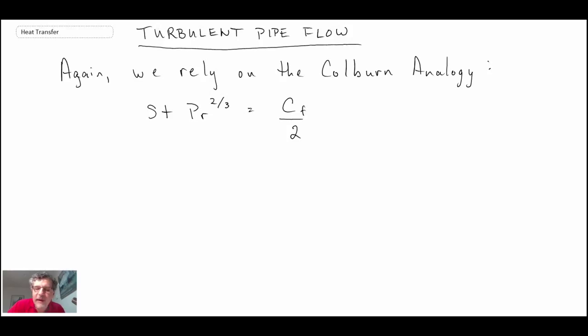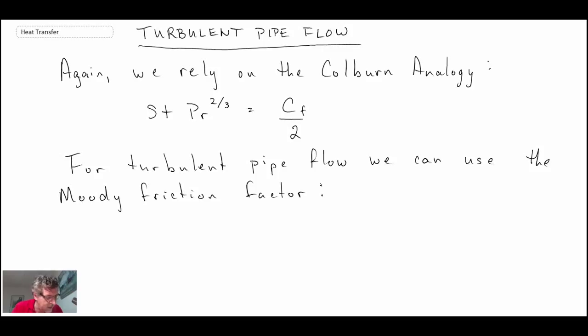So what we're going to do, we're going to come up with the skin friction equivalent for pipe flow. We'll be using the Moody friction factor and this friction factor can either be obtained from the Moody diagram or it could be obtained from something like a Colebrook-White equation. From the friction factor we can relate it to pressure drop and in this expression L is the length of the pipe or the section that this pressure drop pertains to.